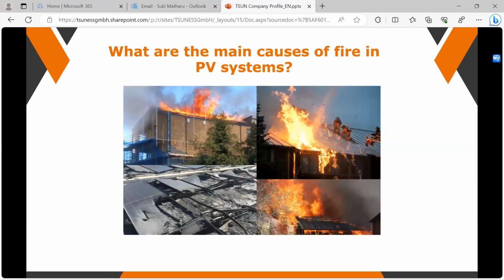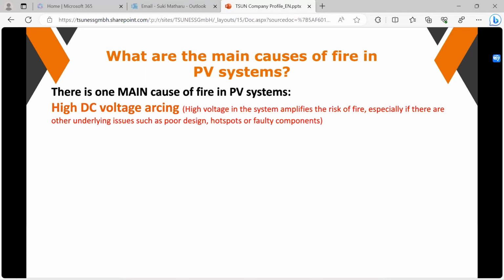So we'll focus, as I said, on the fire side of things and look at what causes fire in PVs. The main cause of a hazardous situation in a PV installation is high DC voltage arcing. As the voltage gets higher and higher across the string, the whole system risk amplifies. The higher the DC voltage, the more amplification there is across the board. A problem that a 40-50 volt DC system would not really be bothered with, because the resistance wouldn't be that high at that level, becomes a big problem as the voltage gets higher.